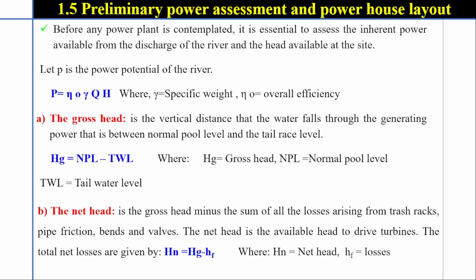1.5 Preliminary power assessment and powerhouse layout. Before any power plant is contemplated, it is essential to assess the inherent power available from the discharge of the river and the head available at the site. Let P be the power potential of the river. P is equal to efficiency times specific weight times discharge times head. The gross head is the vertical distance that the water falls through the generating plant, that is, between normal pool level and the tailwater level.